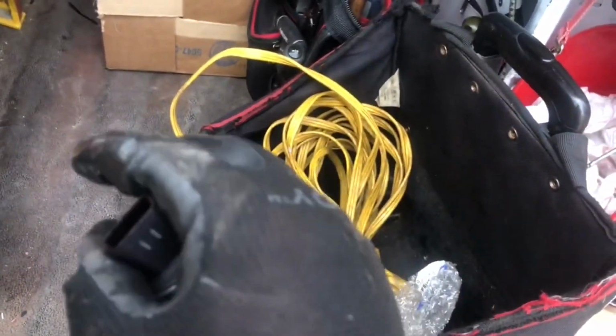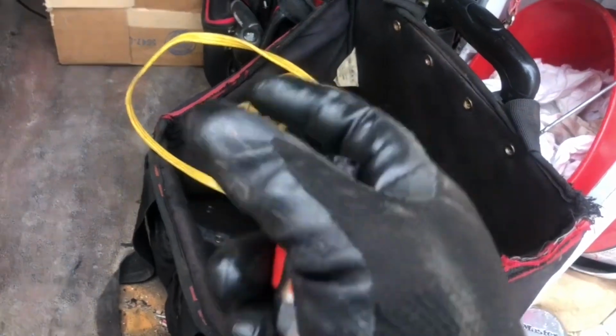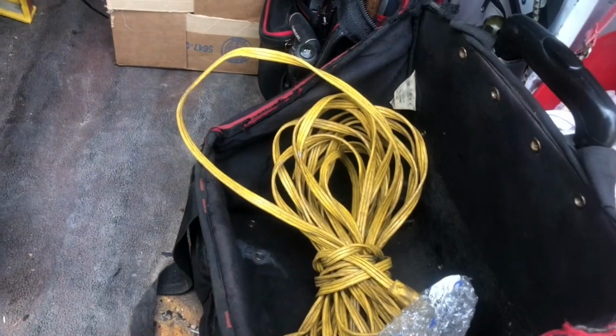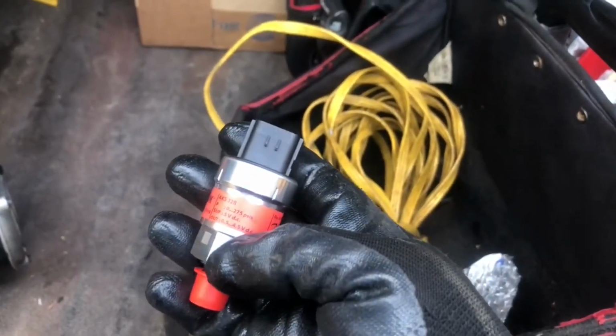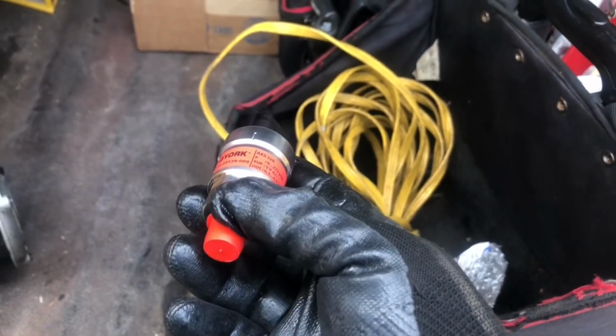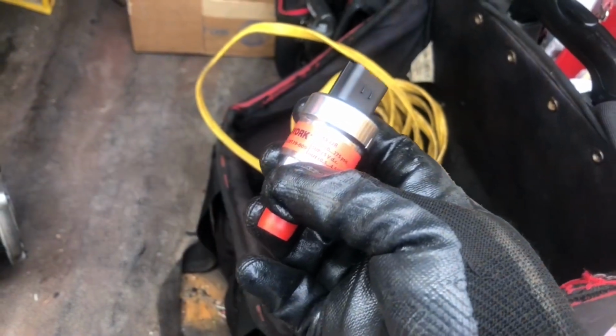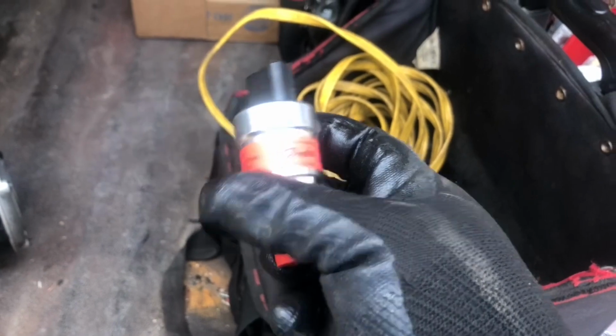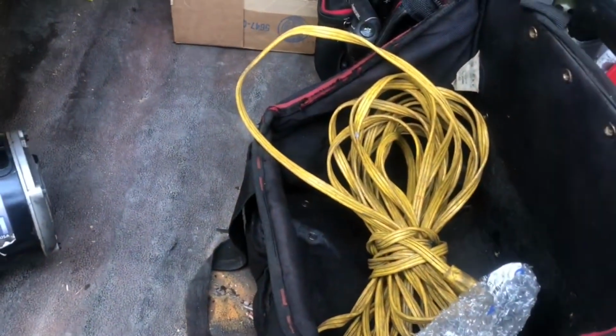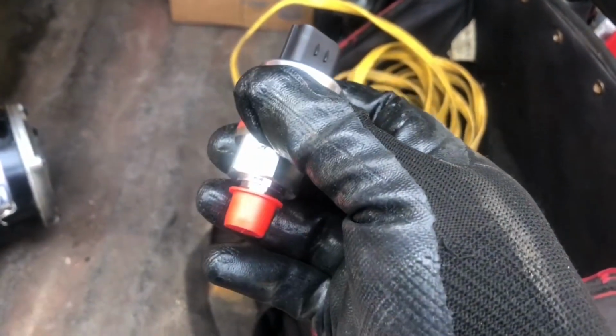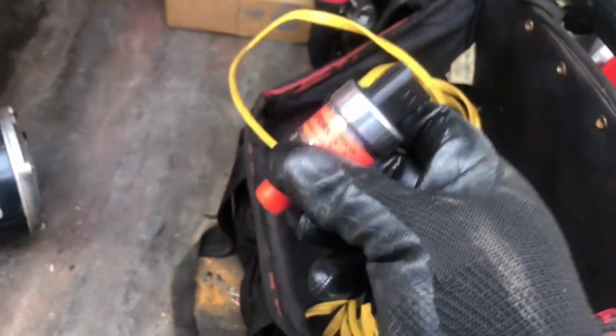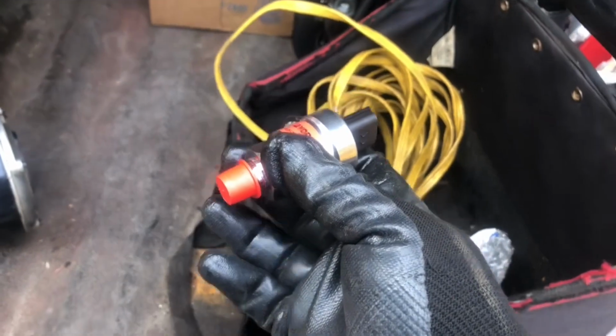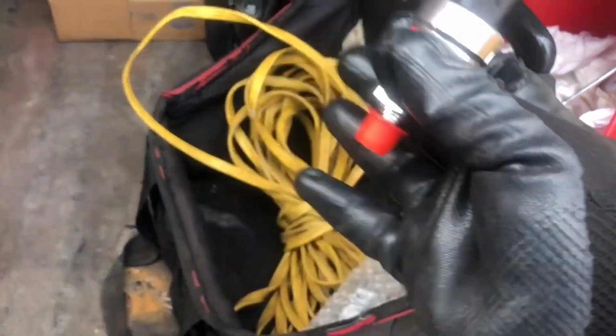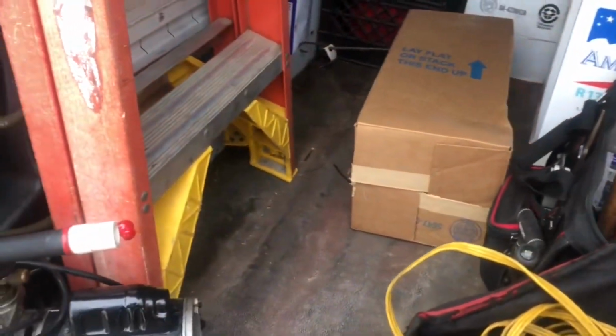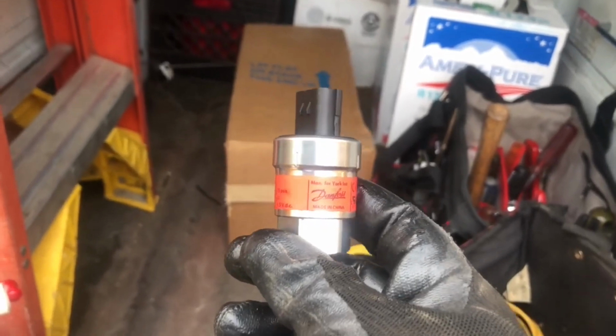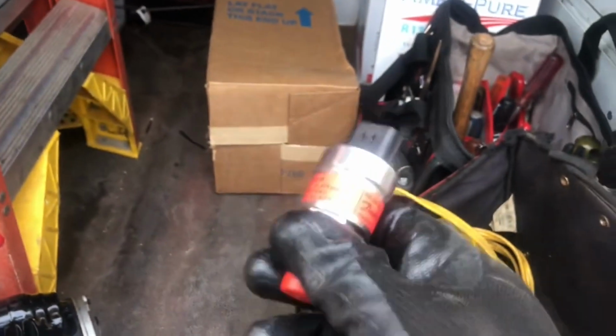If you still have a little pressure, I will still do it. Just be careful, and I'll do it as fast as I can. That way, also, I don't let that much refrigerant go. I have done it that way too, with a little bit of pressure in. Just do it fast so you don't let that much refrigerant go. And it might even be a little better to do it that way. Anyways, but the point is, just be careful whenever you're gonna take it out, because you might still have some refrigerant trapped on that area where this plugs in. It has happened to me. It's not a lot of pressure, but you can still spill oil on your face and get dirty with all that. So stay tuned, that way you'll see the aftermath whenever I'm done replacing this.